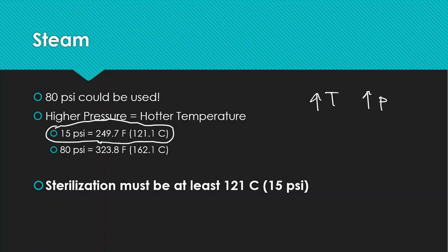This is a very important temperature, and that 121 degrees is going to make sure that sterilization is taking place. So that is the temperature that we need to be working with, and that temperature is simply due to the sterilization that has to happen both in product maybe as well as in all of the materials and equipment that product has come in contact with. We need to sterilize everything that we can.